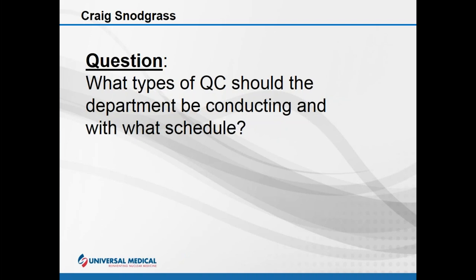Other checks to do would be a COR, or center of rotation, which confirms that your gantry is within specs while performing SPECT studies. Doing a bars QC, whether intrinsically or extrinsically, will confirm the linearity of the detector is good and that it will produce clear, crisp images. Both the COR and the bars QC should be completed on either a weekly or biweekly basis.